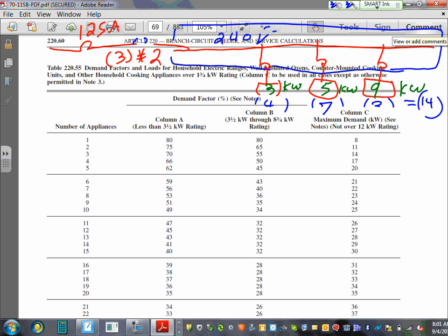That's the feeder. Let's do the branch circuits. How are you going to size the branch circuits? No, the branch circuits are going to be sized one of them at a time, guys. Let's start with this branch circuit right here. I'm going to call this one the 3 kW branch circuit. Here's how you do it. I need you guys to do the math for me. 3,000 divided by 240. Could you please?